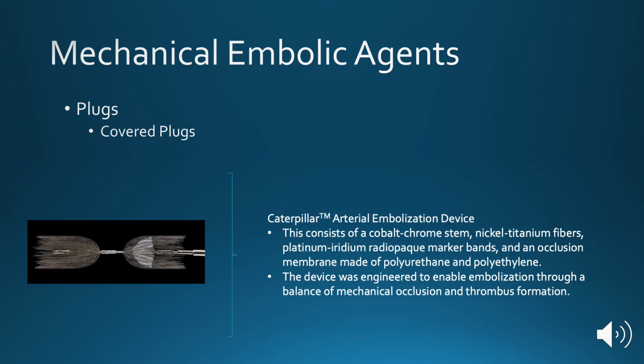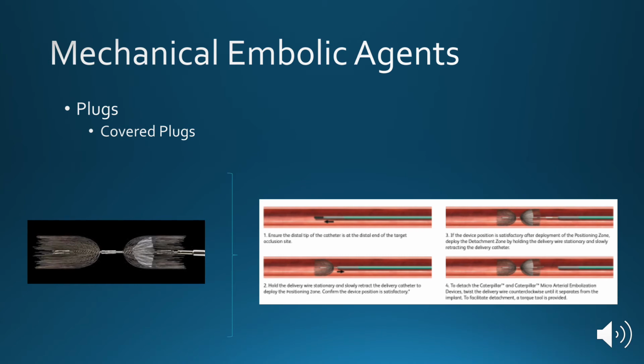The Caterpillar plug is another one of these new plugs. This consists of a cobalt chrome stem, nickel titanium fibers, and platinum iridium marker bands, as well as an occlusion membrane that's made of polyurethane and polyethylene. The device was engineered to enable embolization through a balance of mechanical occlusion by the occlusion membrane and thrombus formation within the nickel titanium fibers. The device is delivered through an appropriately sized catheter and then uncovered. Once the first half is completely uncovered, it can no longer be retracted back into the catheter. And once the device is deployed in its entirety, you have to turn the pusher wire in order to release the plug into the vessel.